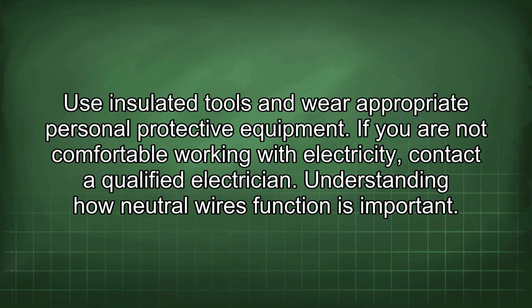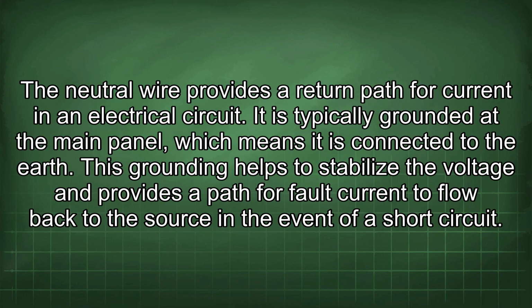Understanding how neutral wires function is important. The neutral wire provides a return path for current in an electrical circuit. It is typically grounded at the main panel, which means it is connected to the earth. This grounding helps to stabilize the voltage and provides a path for fault current to flow back to the source in the event of a short circuit.